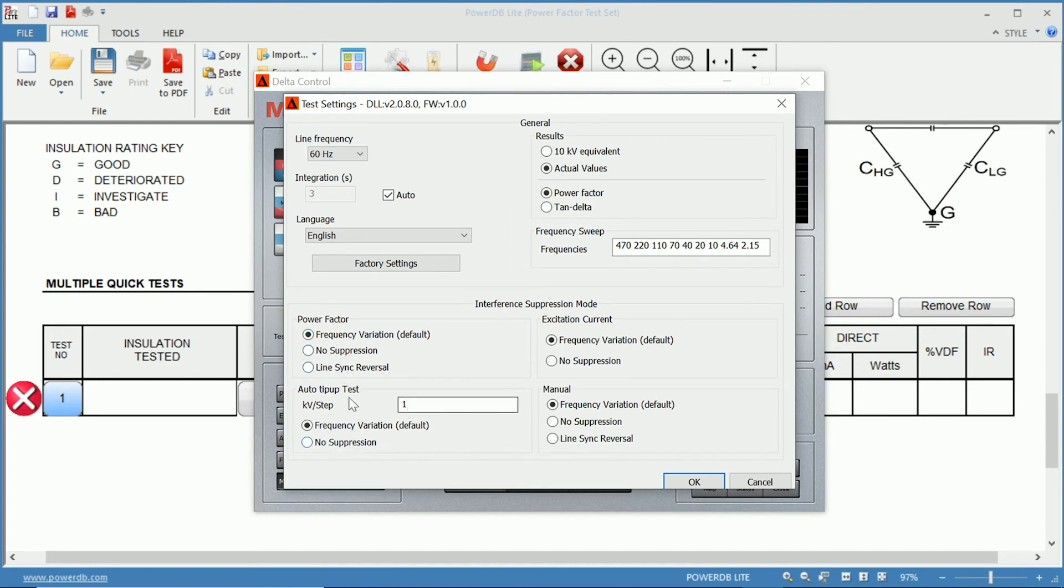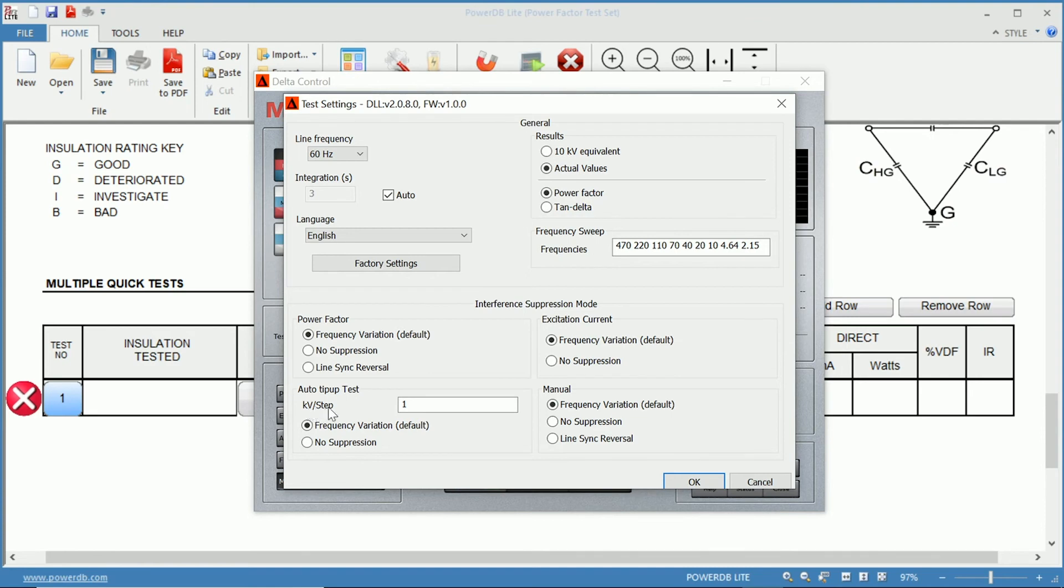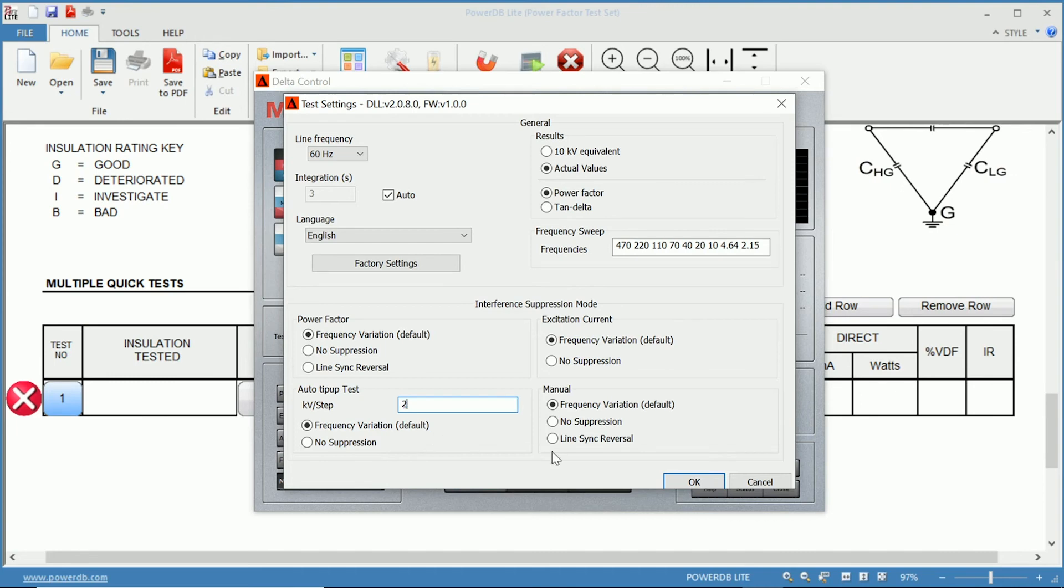And here's where you also can configure your tip-up test. So if you're performing a tip-up test, you can choose your kilovolts per step and your suppression you want during your tip-up test. So if you wanted to perform a tip-up test to 10 kV and 2 kV steps, you could set that up here.